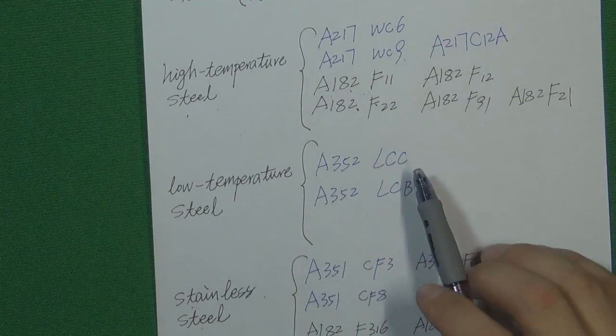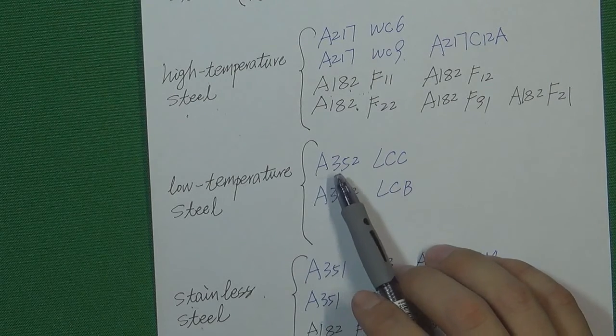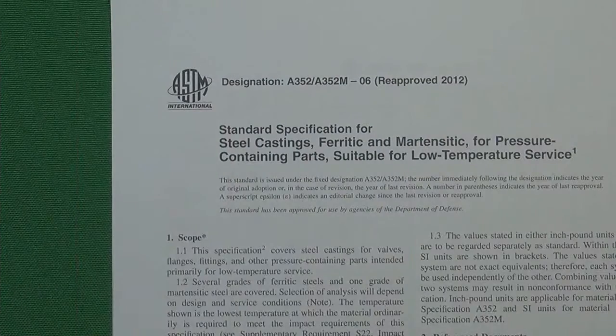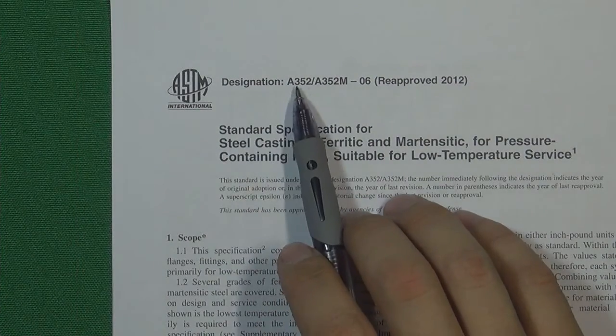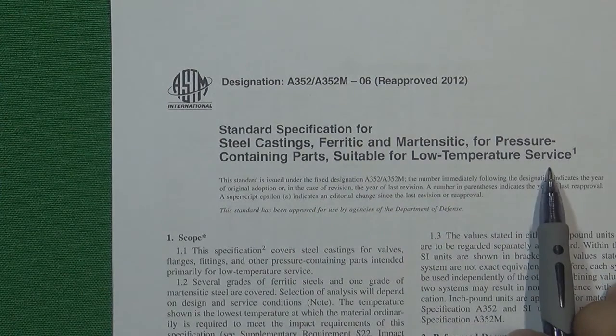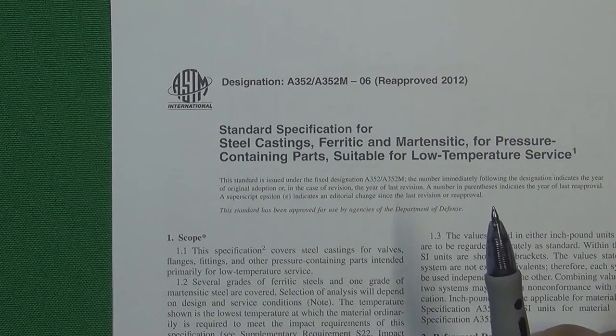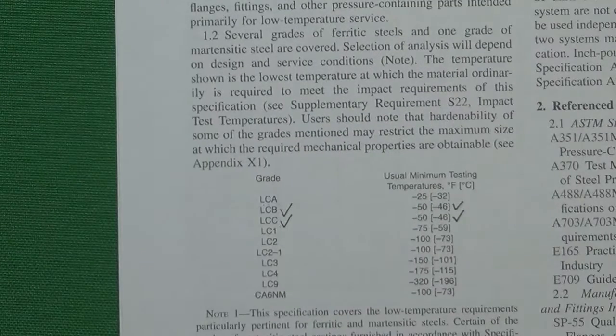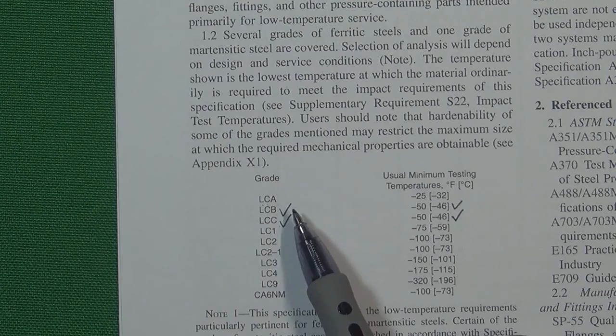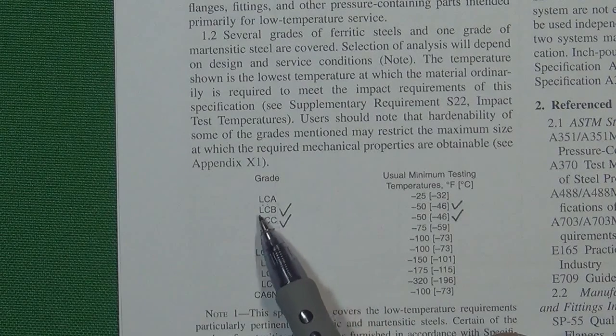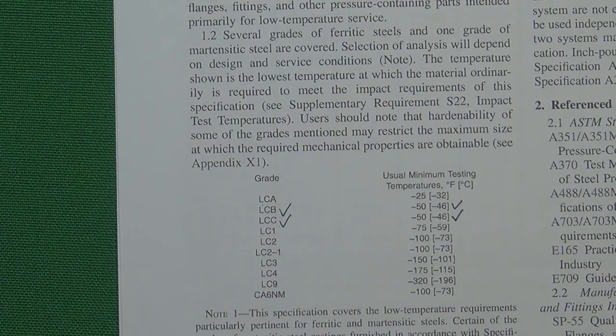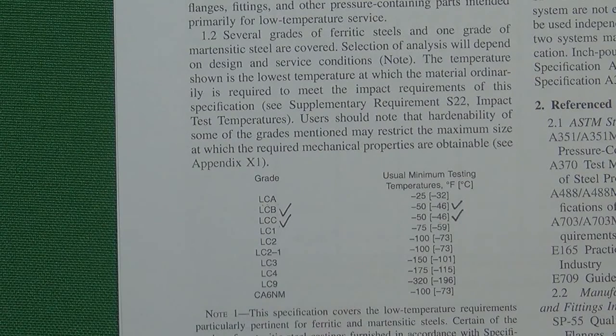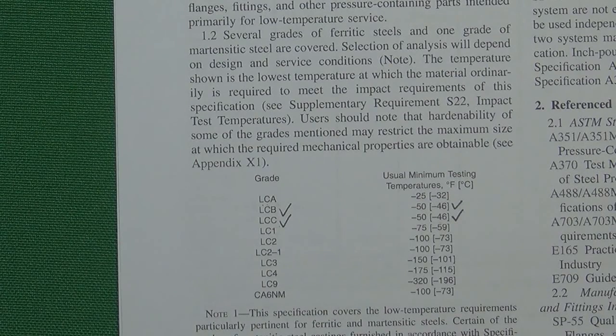Let's look at the standard for low temperature steel, ASTM A352. This is the standard for low temperature service steel. According to the standard, it contains several different grades — LCA, LCB, and LCC. The most common two materials for the valve industry are LCB and LCC. B is better than A, C is better than B — the same principle as carbon steel. L means low temperature, C means carbon.